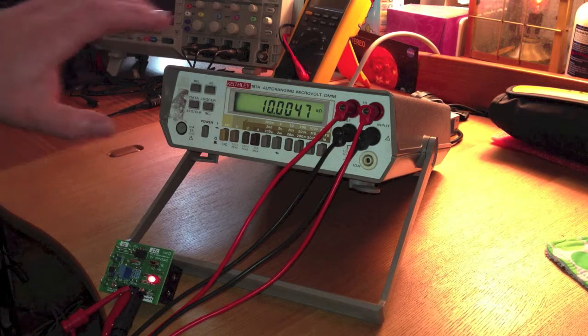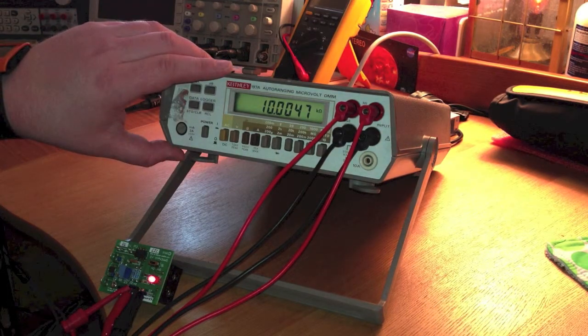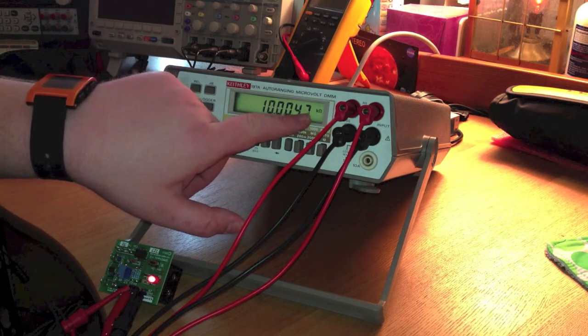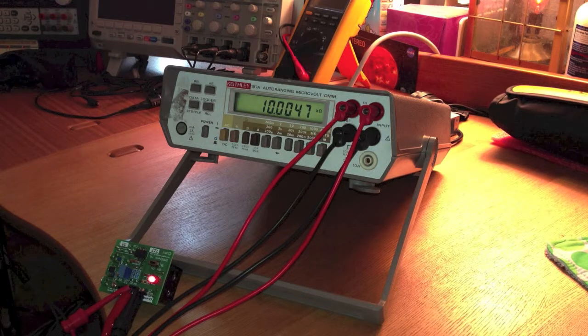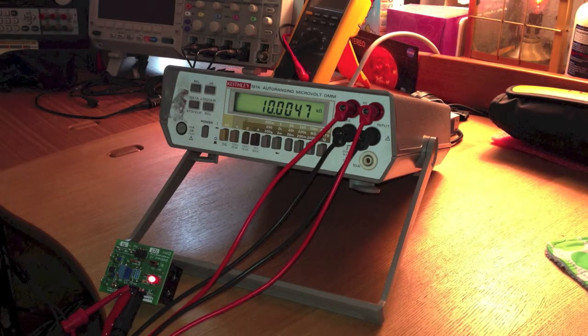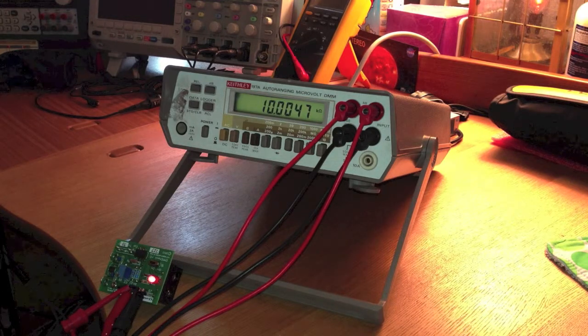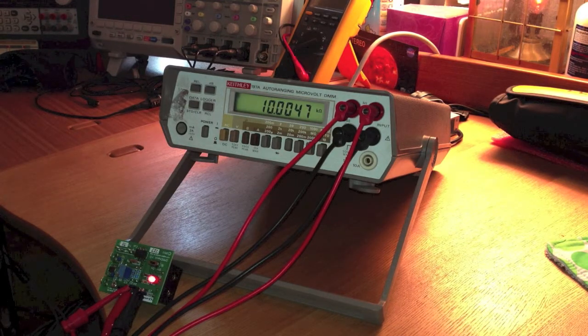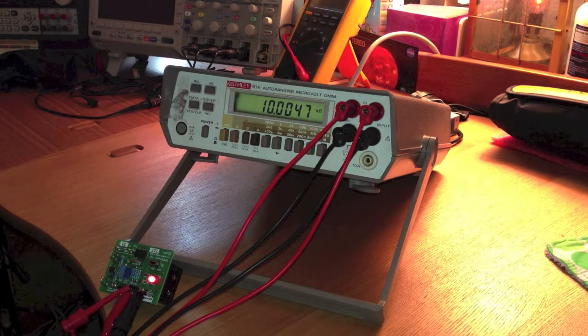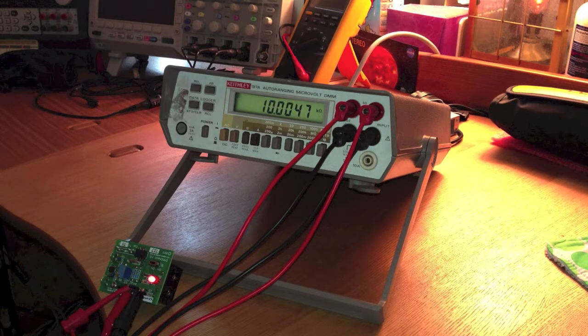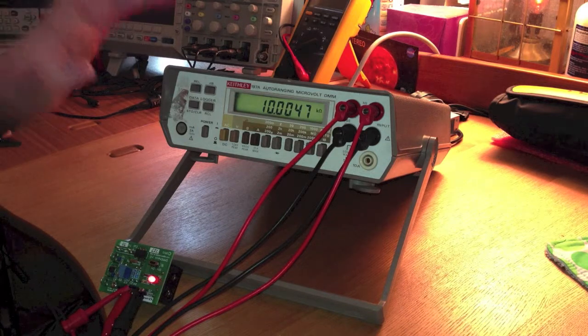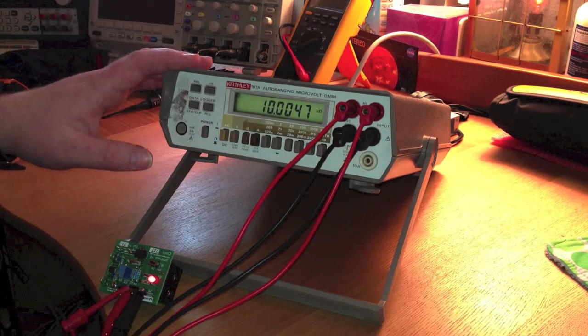Out of the box, this unit is three counts off. On this range, this should be 10.0050K and we're at 10.0047K. So I think that's acceptable given the actual stated accuracy of this unit.